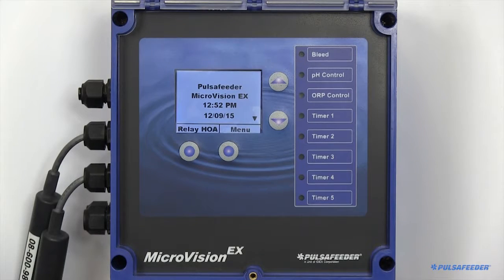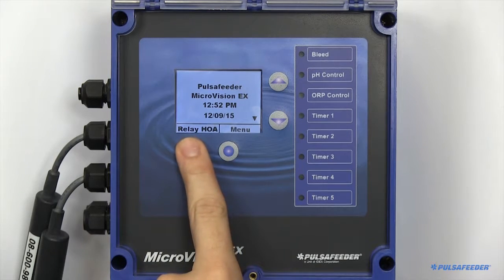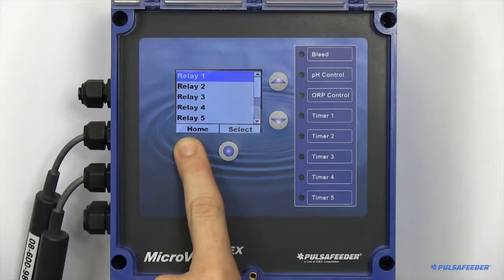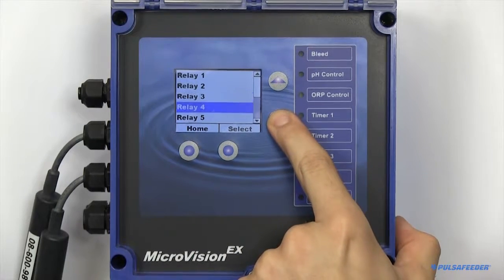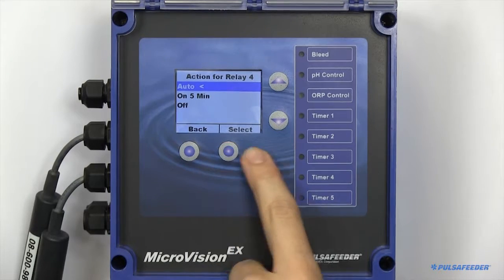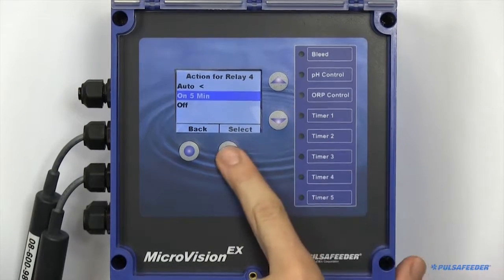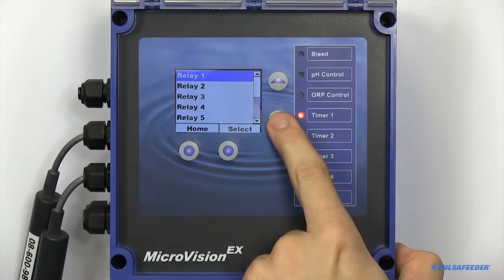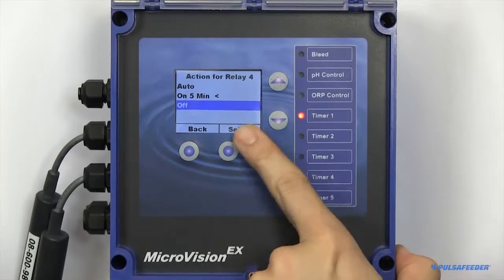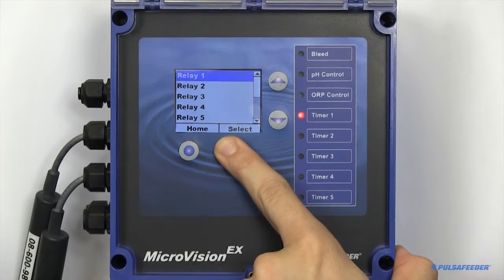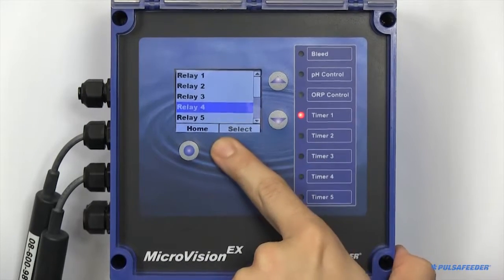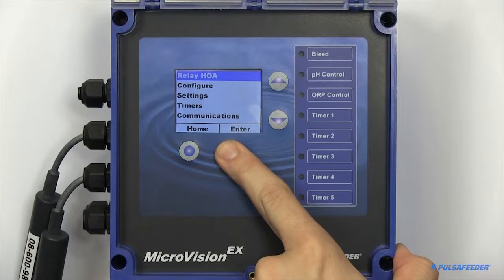The HOA function, or hand, off, auto, is a useful feature for servicing your pumps or troubleshooting any electrical problems. To access the HOA screen, you can simply press the bottom left button from the home screen. You next select the relay you would like to adjust. You can set each relay to either on for 5 minutes, off, or have the relay respond to your normal programming by setting it to auto.